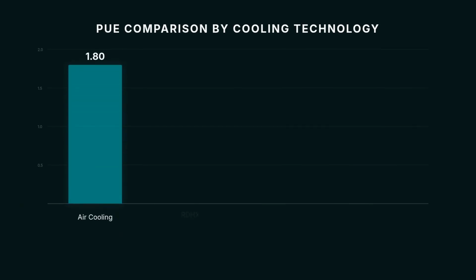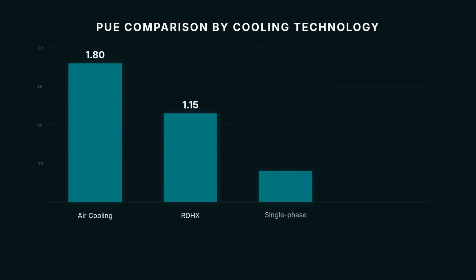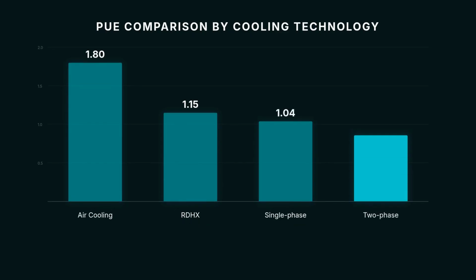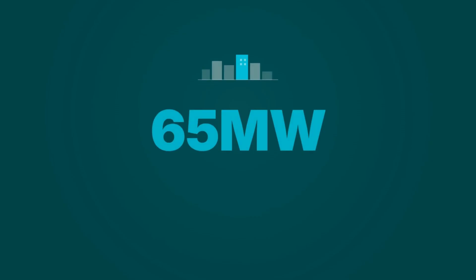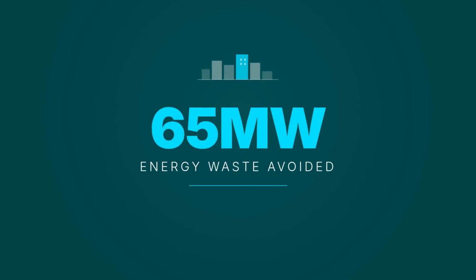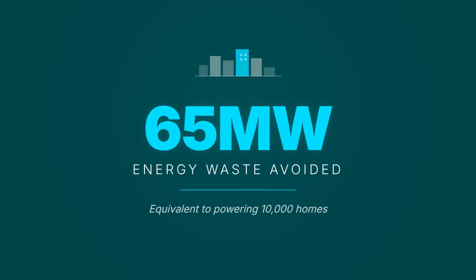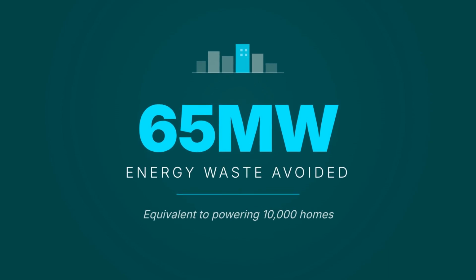Let's compare the PUE across these technologies. Air cooling sits at 1.8. Two-phase immersion reaches 1.02. At 85 megawatts of IT load, the difference is 65 megawatts of wasted energy, enough to power a small city. The financial impact is staggering, representing an annual saving of approximately £390 million.